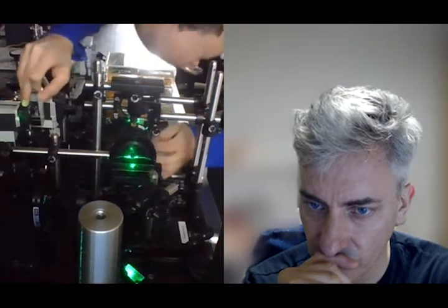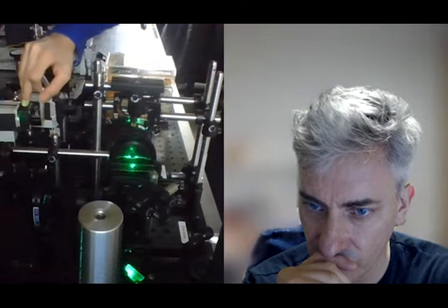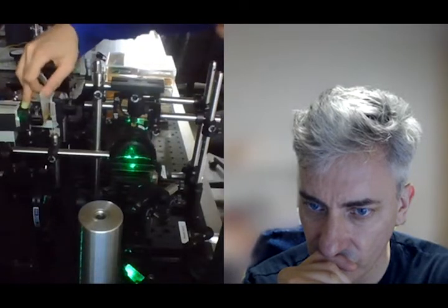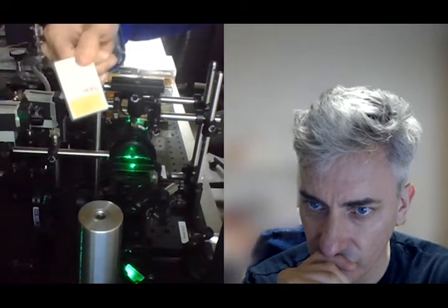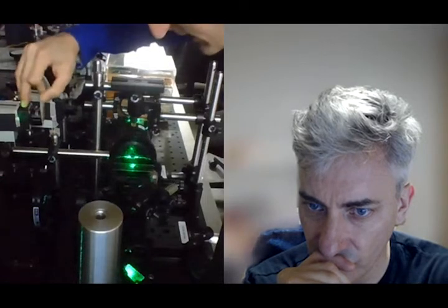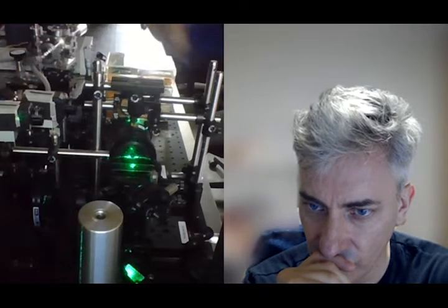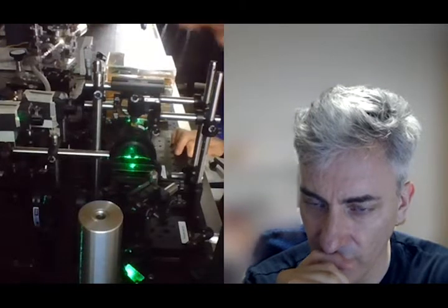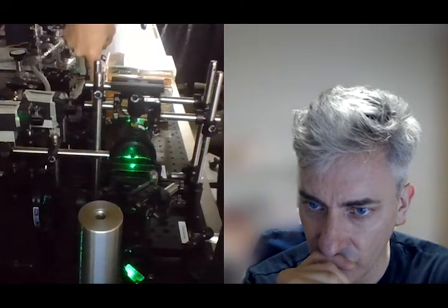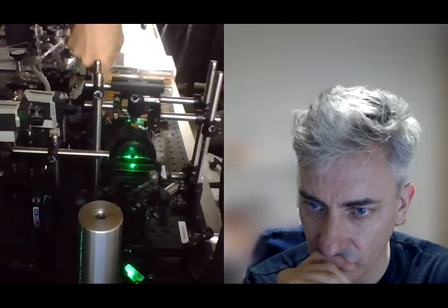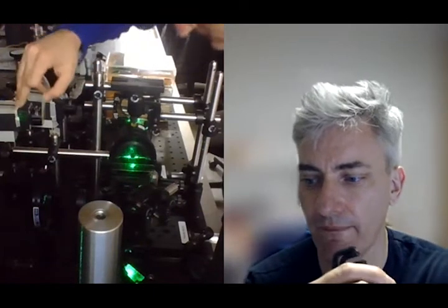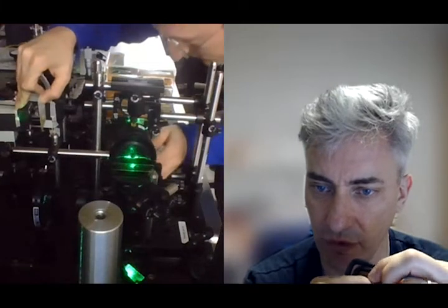And it's massively misaligned. So I don't know if you can see where I am now. I'm taking the card to try to put it at the detector, and the spot is very far off from the center. Right. So I'm going to use this pick-off mirror and this one to try and push the spot towards the center of the detector. Sure.